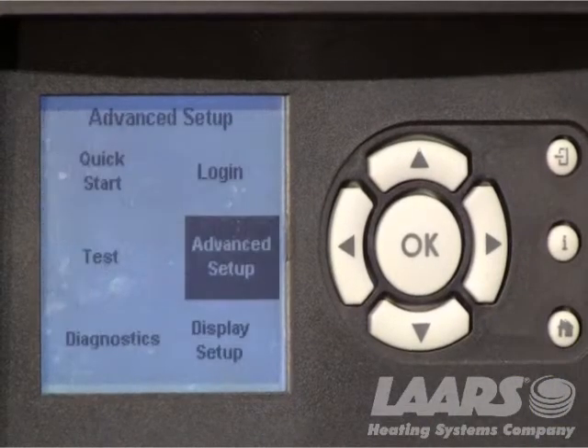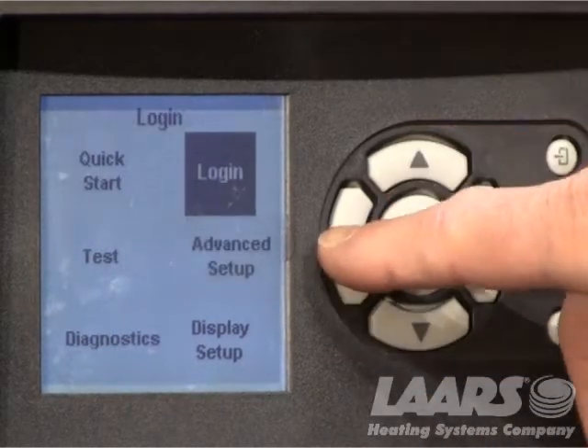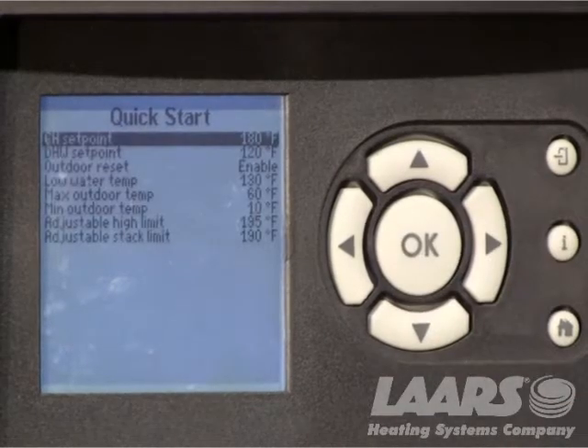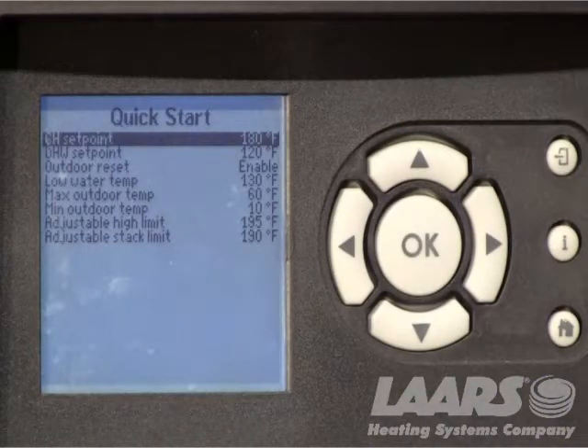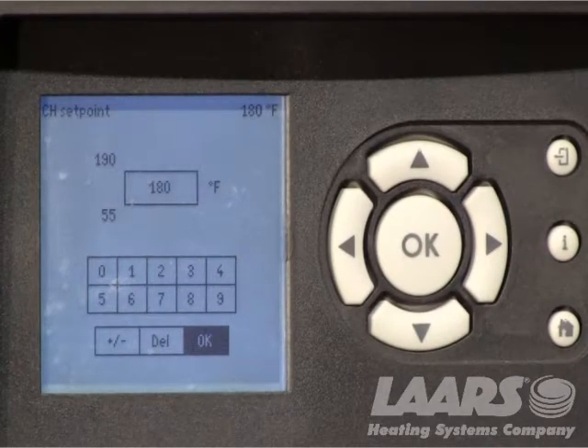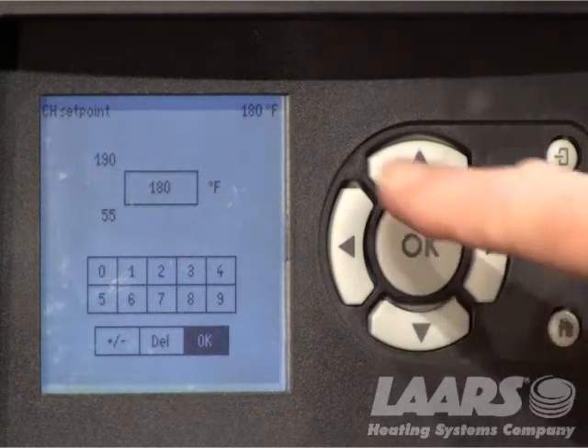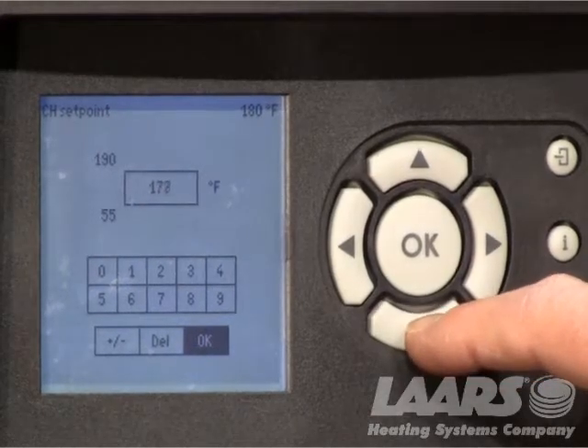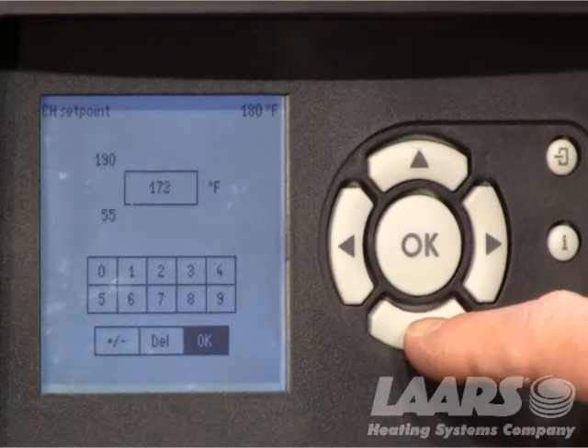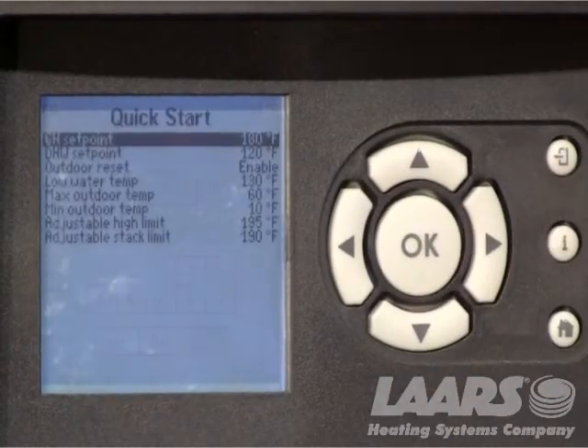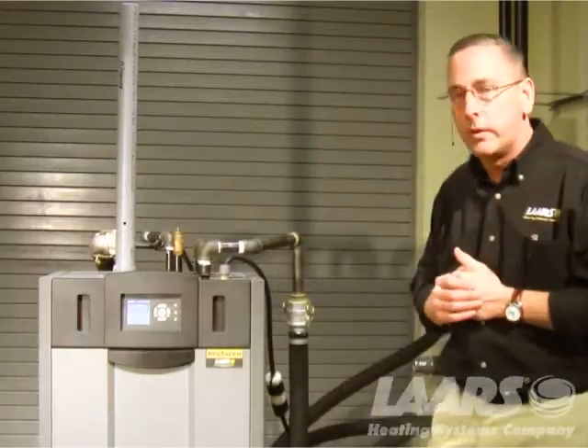What we would do is press the information button. You can use your up and down arrows to go over and highlight Quick Start. Once Quick Start is highlighted, press the okay button and it will bring us to the Quick Start menu. Right here, central heat is highlighted. Click okay and now you can adjust your central heat set point simply by using your up and down arrows. Presently I have it set for 180, but for this example let's say I only wanted 170 degrees. I'll use my down arrow to highlight 170. Once I've got 170 on the screen, I simply press the okay button. Now my central heat set point is locked in for 170 degrees.